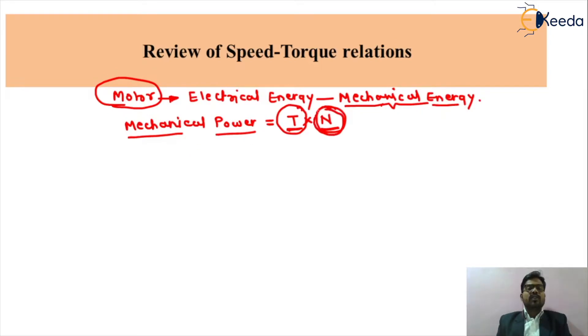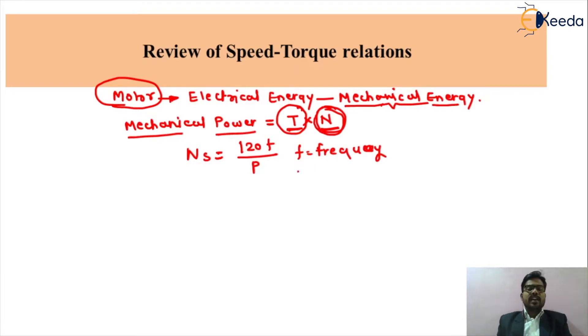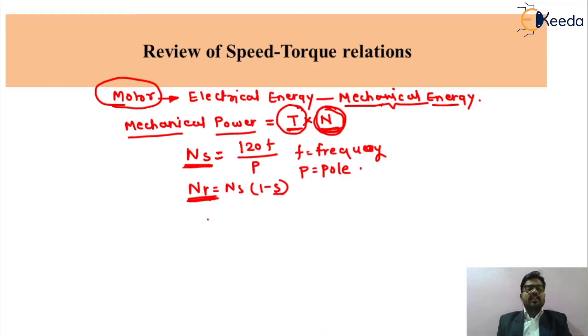For the induction motor, the synchronous speed is the speed of the rotating magnetic field, given by Ns = 120F / P, where F is frequency and P is the number of poles. The rotor speed is given by Nr = Ns × (1 - S), where slip S = (Ns - Nr) / Ns.